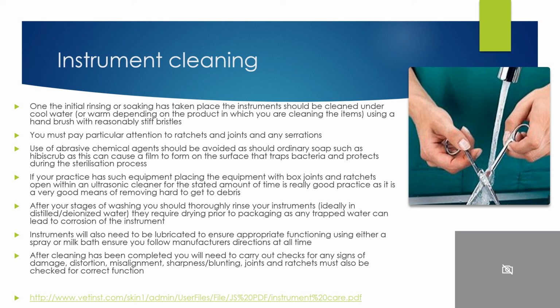Once the initial rinsing or soaking has taken place, the instrument should be cleaned under cool water or warm depending on the product in which you are cleaning the items, using a hand brush with reasonably stiff bristles. You must pay particular attention to ratchets and joints and any serrations. Use of abrasive chemical agents should be avoided, as should ordinary soap such as Hibiscrub, as this can cause a film to form on the surface that traps bacteria and protects them during the sterilisation process.